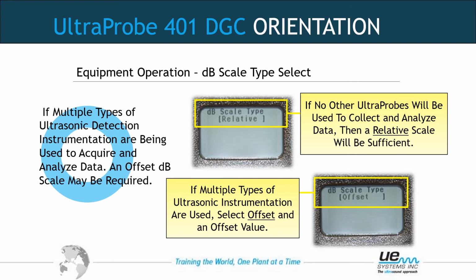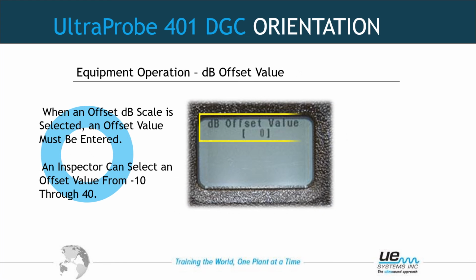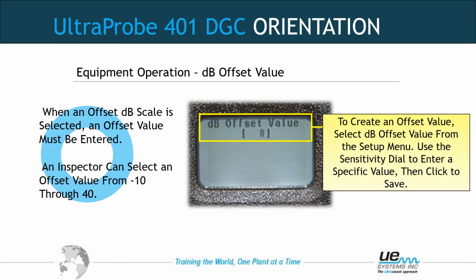Let's say the 401 reads 44, a difference of 8 decibels. Remember, the 10,000 read 52. We're now reading 44. So what we would do is come to dB scale type select in the menu on the 401, and then change the scale from relative to offset. Next, we would rotate in the menu. Once we chose offset, we would go back into the menu. The next item down would be dB offset value.